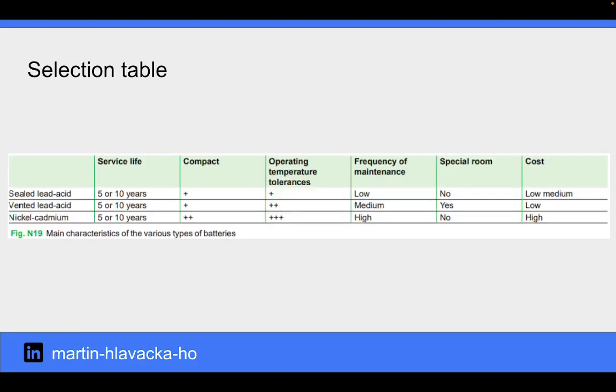Here we can see a table that sums up the main characteristics of the various types of batteries. Increasingly, recombination batteries would seem to be the market choice for no maintenance, easy implementation, and installation in all types of rooms. In certain cases, however, vented batteries are preferred, notably for long service life, long backup times, and high power ratings. Vented batteries must be installed in special rooms, complying with precise regulations, and require appropriate maintenance.